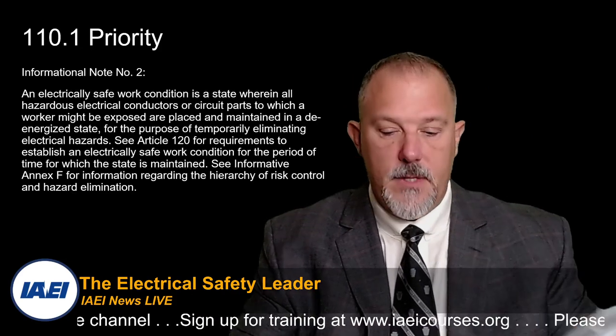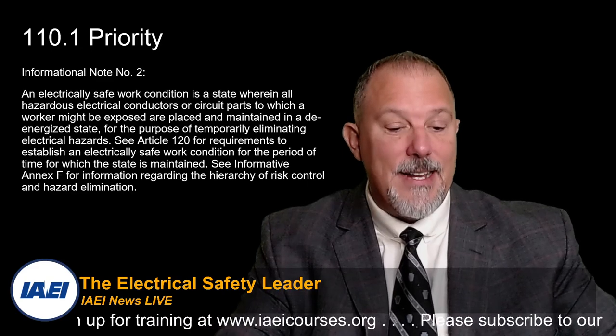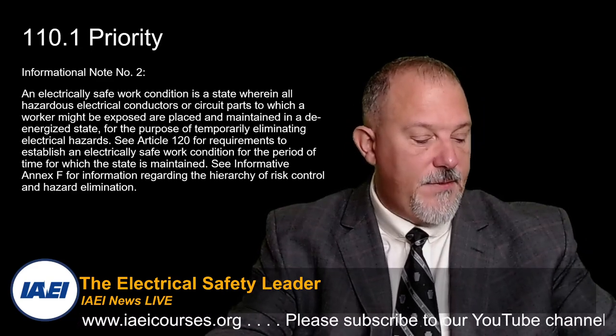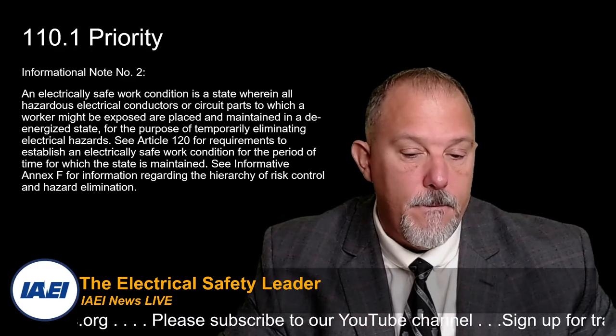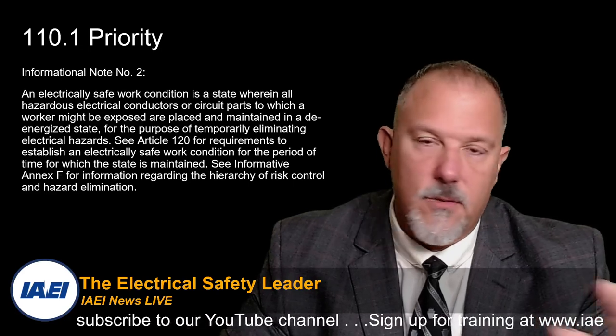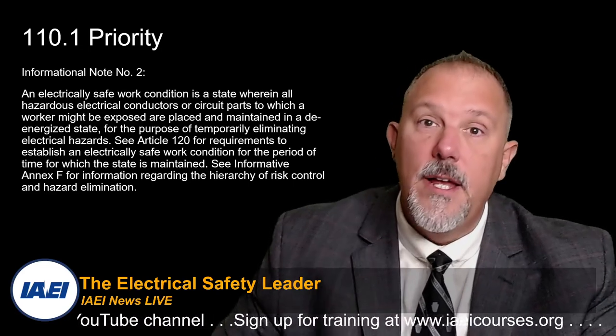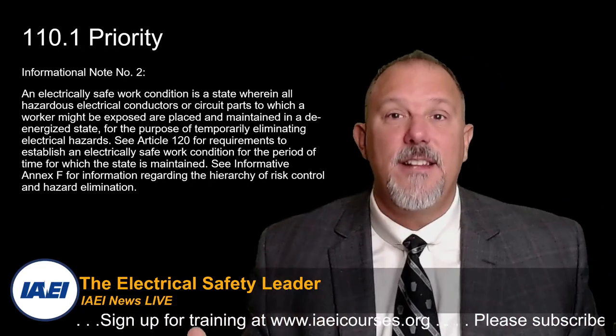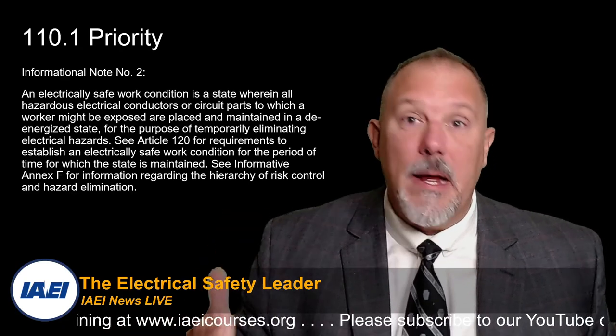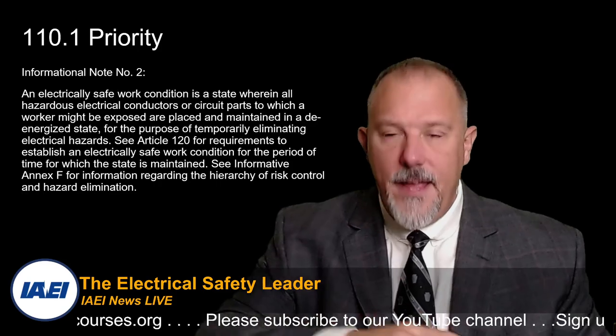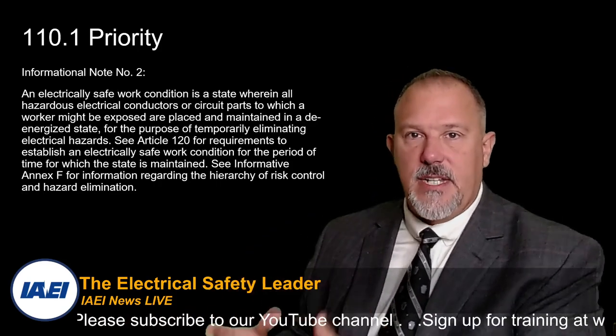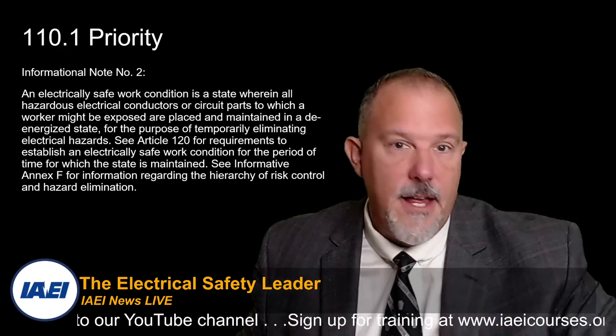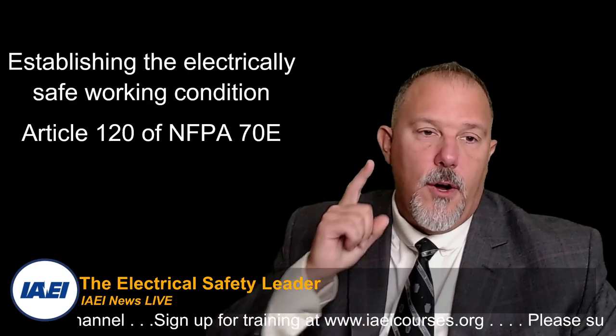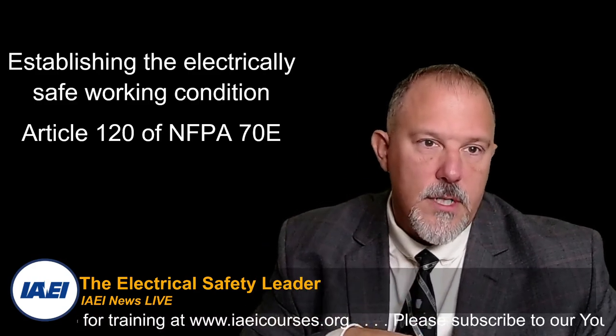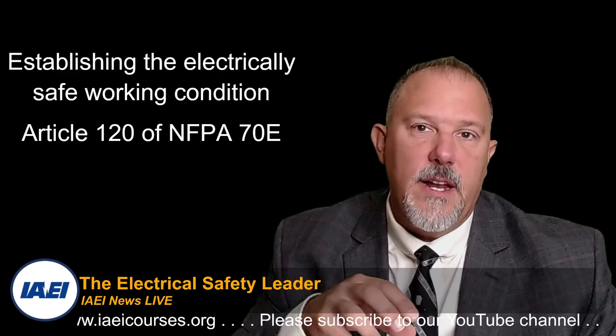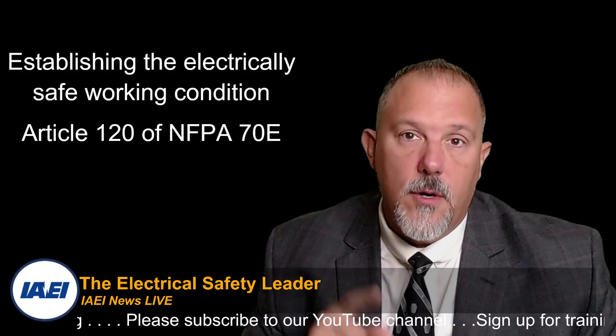Article 120 of 70E is titled Establishing an Electrically Safe Work Condition. And it's found on page 70E-20. And you'll notice that this article just kicks everything off with lockout tagout program. So if you're not familiar with lockout tagout, that's a challenge for you in establishing and meeting the top priority of 70E. So we have to understand the hazards, and then we need to understand how to establish an electrically safe work condition. And this discussion is about understanding the hazards. So you remember, Article 120 contains important information for you when you're developing your electrical safety program.